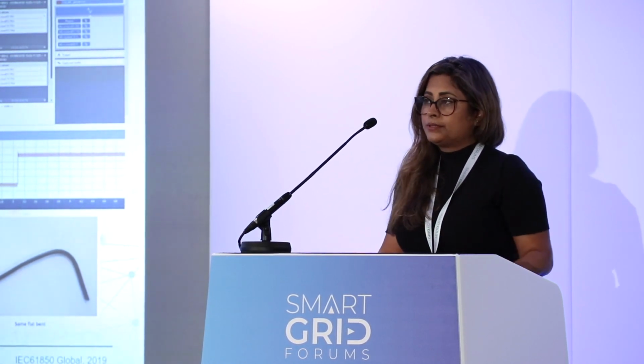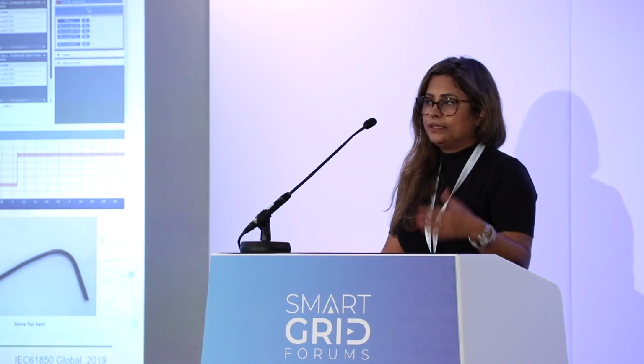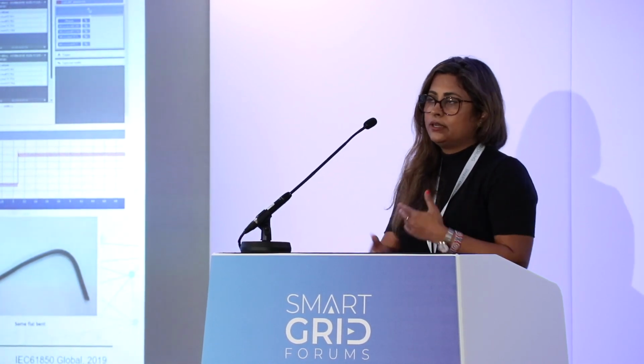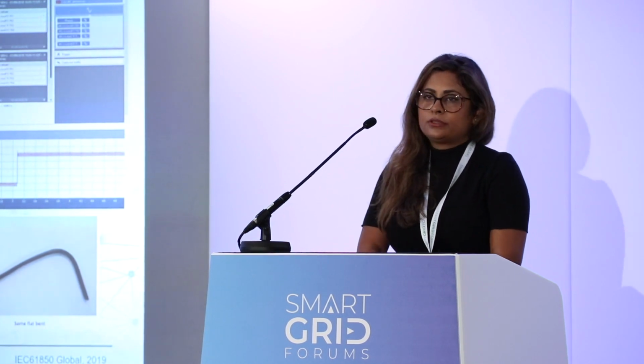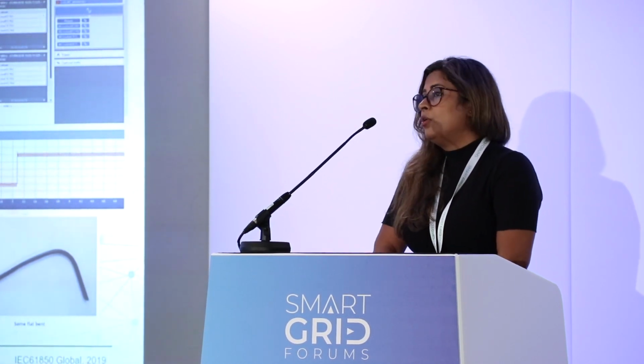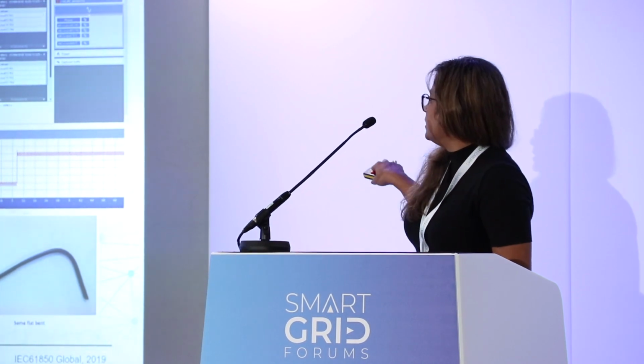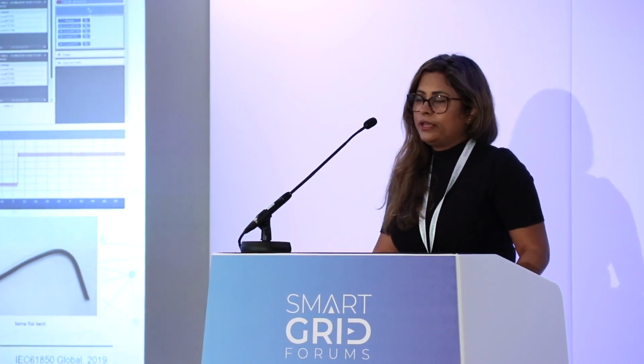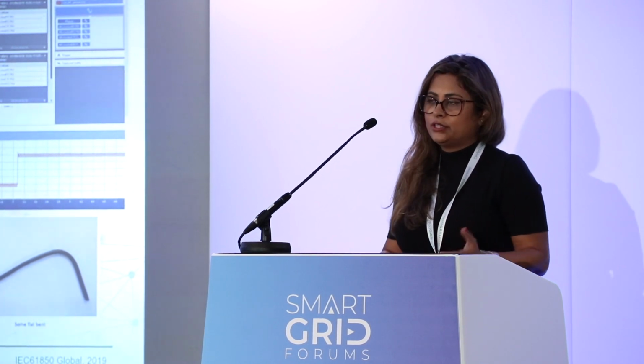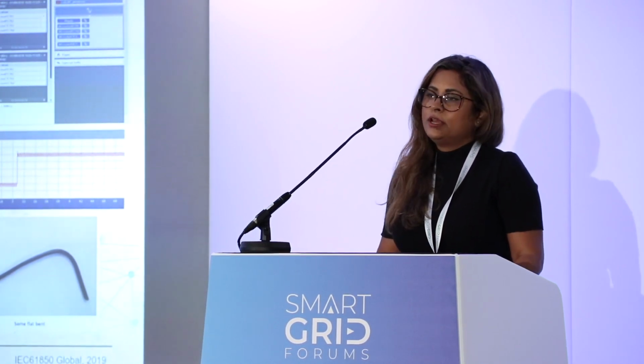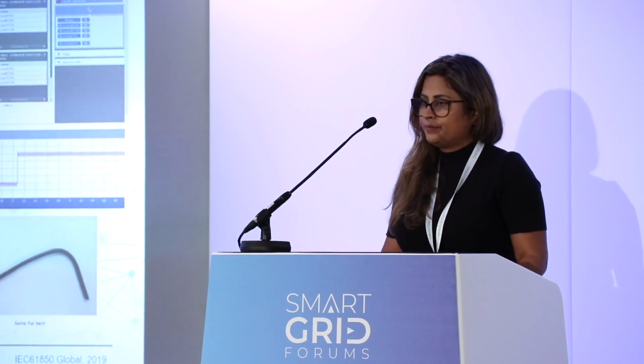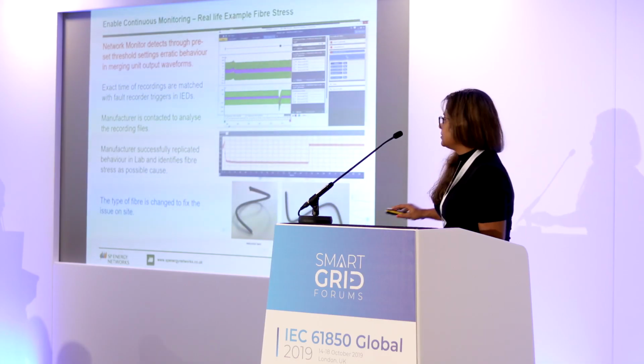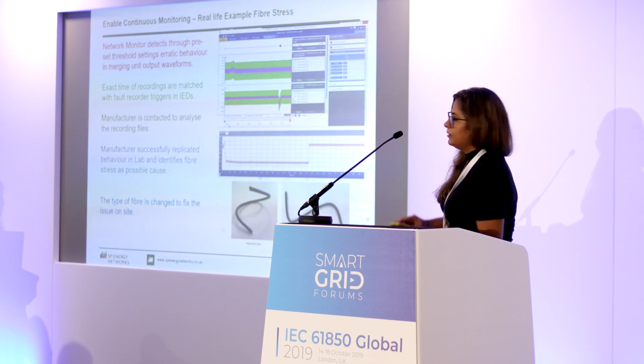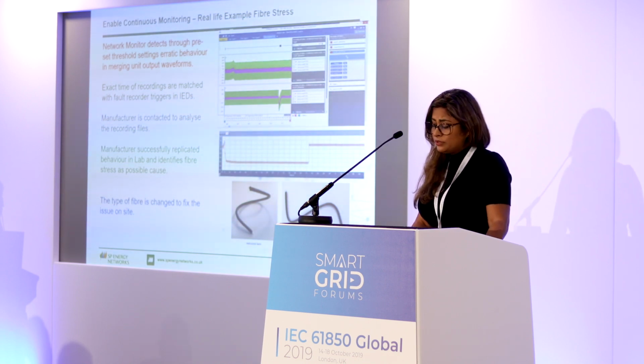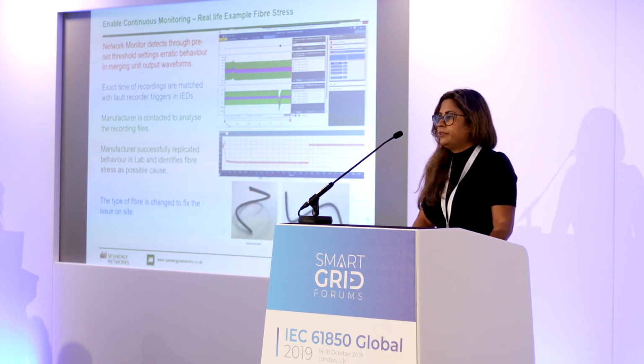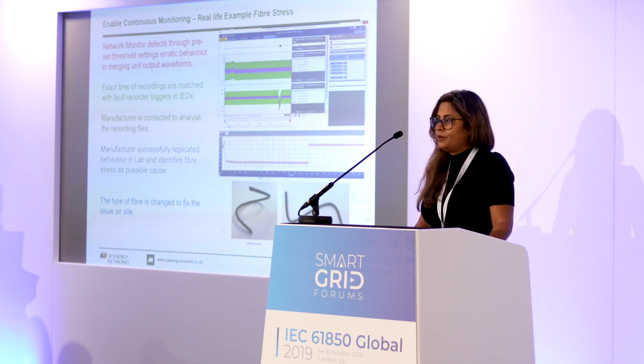Of course, if the fault recorder is picking up a measurement, you can see that the sample values, or all the signal it's seeing, is not right. So we enabled continuous monitoring on the network. We used one of those devices that can do trigger-based recording, and we set a trigger for any deviation in the sample value threshold to be recorded for a period of 10 seconds. After we did that, a couple of times we captured waveforms that were clearly not right. So we were able to extract the records and send them to the vendor for further analysis.